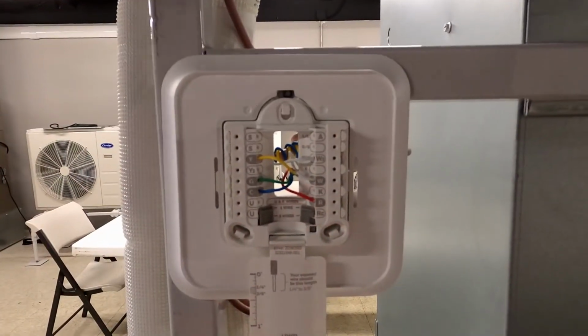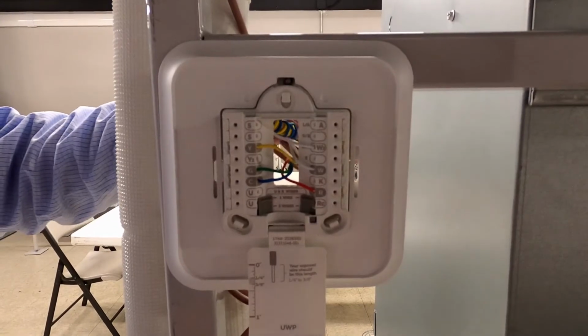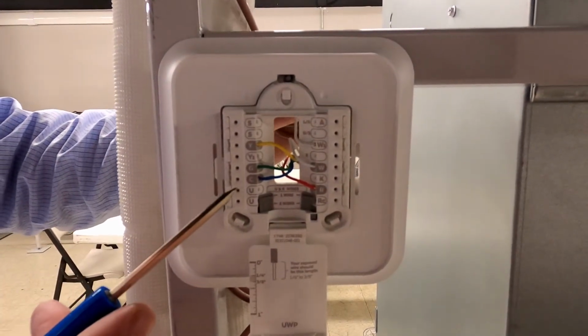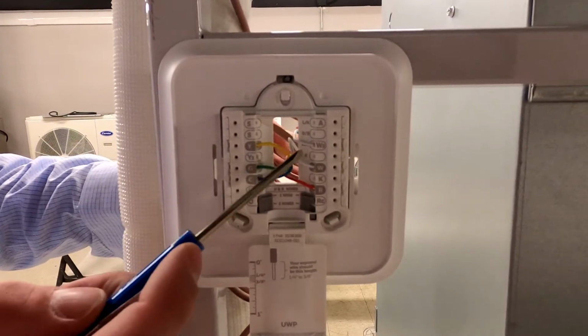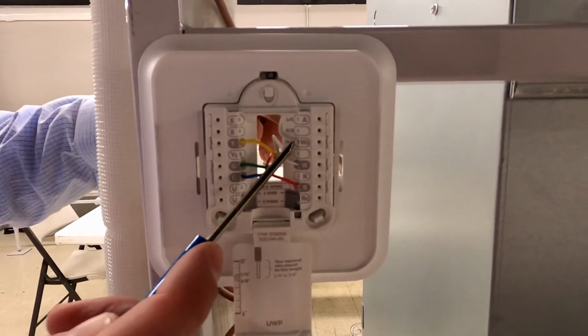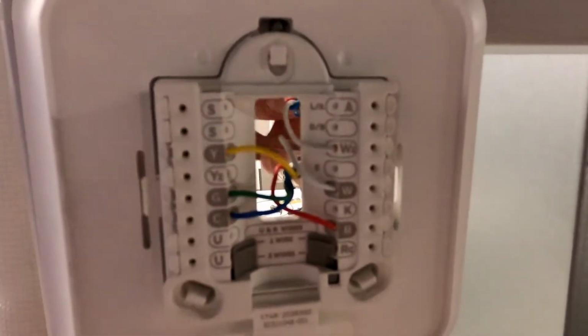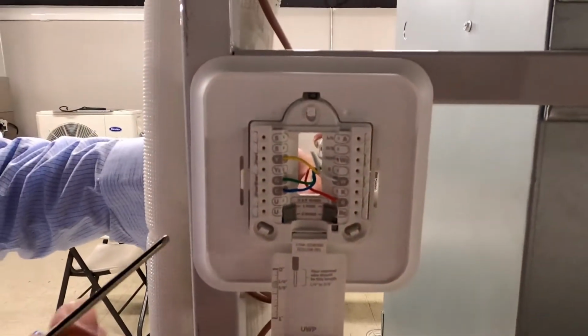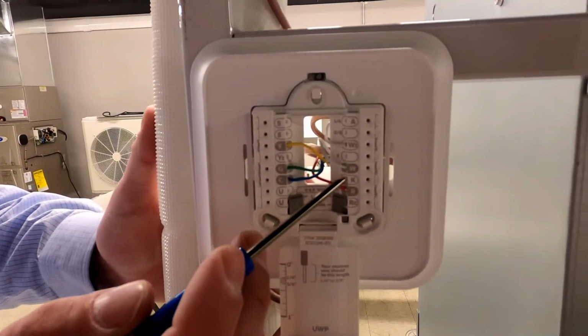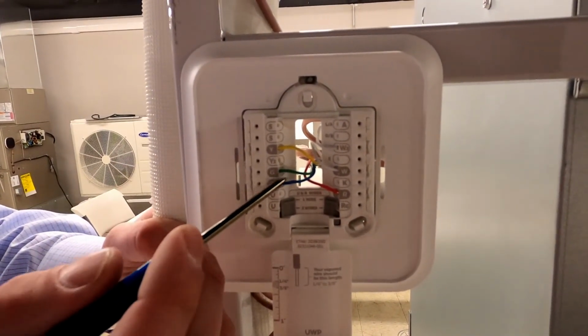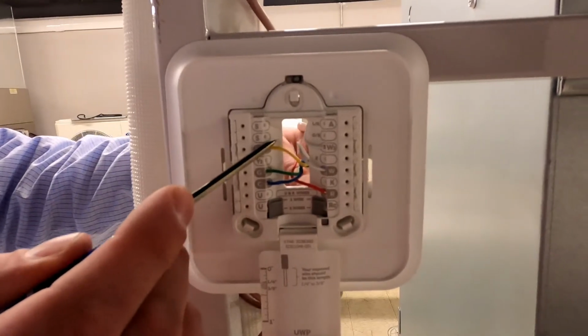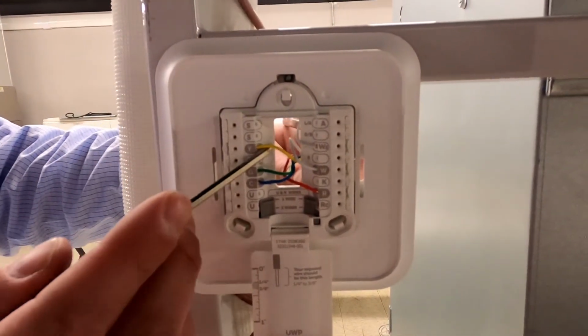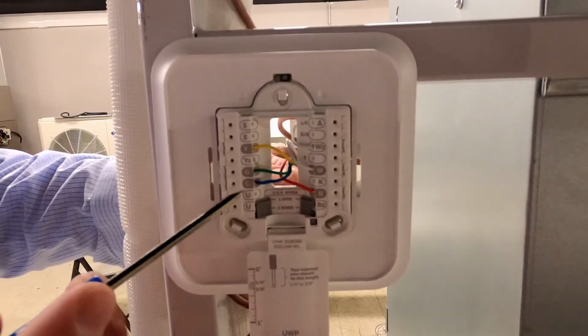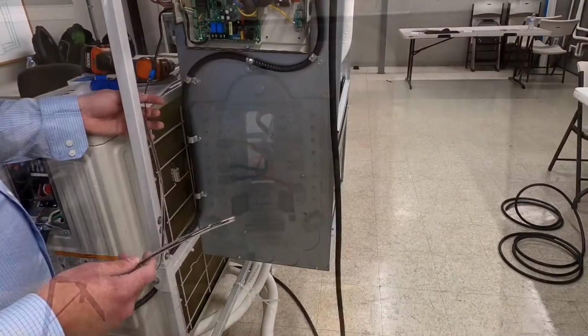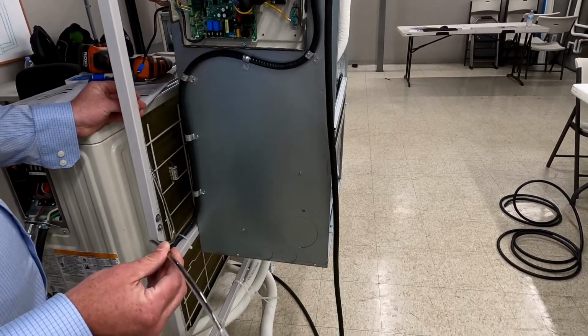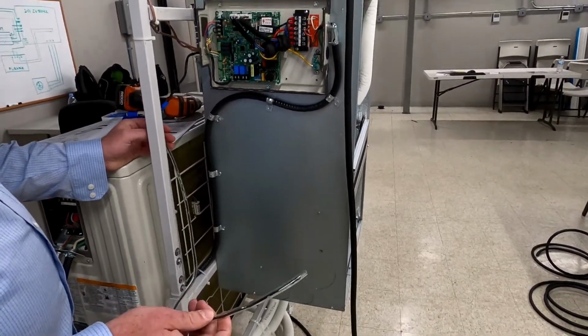When we're hooking up the wires at our thermostat, we have 2 sets of wires. One of the sets of wires only uses 1 wire, and that's W2, which goes directly to the air handler to energize electric heat. Our other set of wires is our W, R, C, G, and Y. And those go to the interface kit to give the interface kit the command to either run heating or cooling, or fan only.